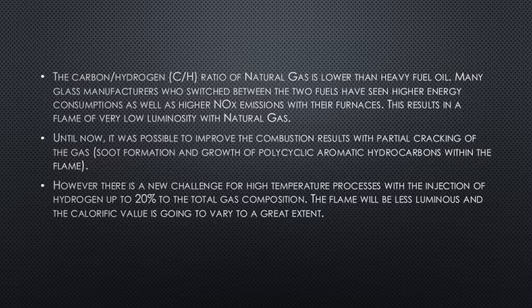This results in a flame of very low luminosity, and until now it was possible to improve the combustion results with the help of partial cracking of the gas, that is the formation and growth of polycyclic aromatic hydrocarbons within the flame. But a new challenge for high temperature processes is the injection of hydrogen up to 20% of the total gas composition. The flame will be less luminous and the calorific value can vary to a very high extent.